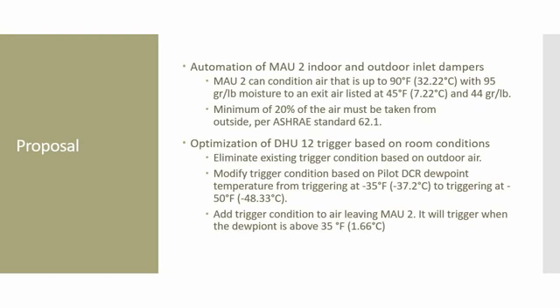Another proposed idea is to optimize the DHU12 trigger conditions. Currently, the equipment is turning on and off based on the room conditions and outdoor air temperature. This is a reactive measure. We want to be proactive to ensure the room never gets out of specification. We are going to have this unit be triggered by the air dew point temperature that leaves MAU2 and update the trigger condition for the dew point in the room.